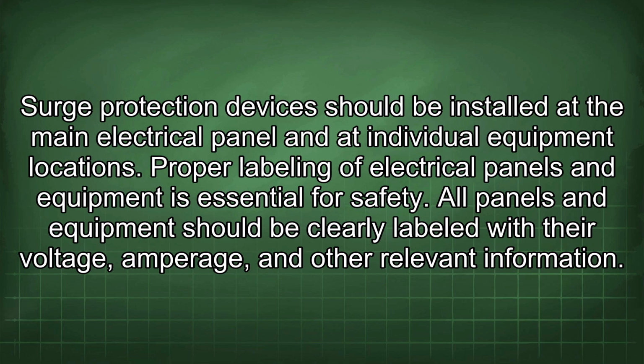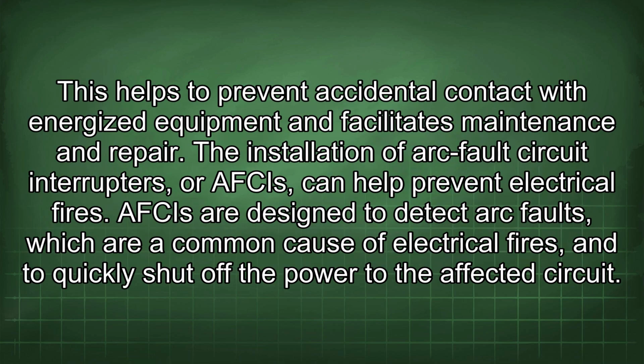Proper labeling of electrical panels and equipment is essential for safety. All panels and equipment should be clearly labeled with their voltage, amperage, and other relevant information. This helps to prevent accidental contact with energized equipment and facilitates maintenance and repair. The installation of arc fault circuit interrupters, or AFCIs, can help prevent electrical fires. AFCIs are designed to detect arc faults, which are a common cause of electrical fires, and to quickly shut off the power to the affected circuit.